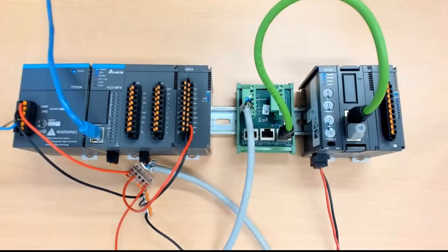Okay, there is another question. Does distance affect the baud rate? Yes. When you choose 1000K, for instance, if I'm not wrong, it is 25 meters. If you choose less than 1000K, I guess it's sequential. If you choose 500K, then it is 50 meters. If you choose 125K, it's 100 meters or something. So it depends on your bit rate. The distance changes.